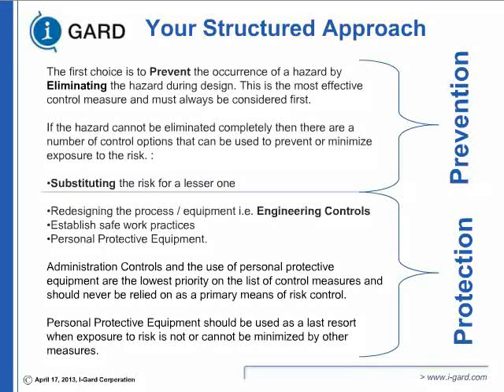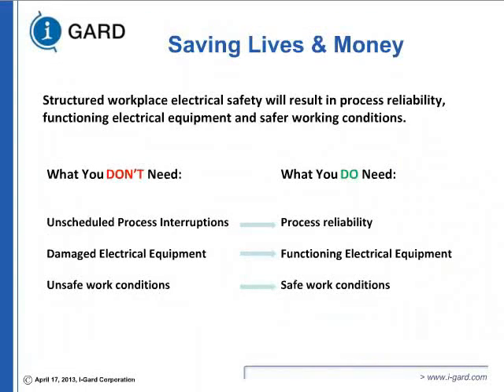Ideal is prevention, by using equipment that will prevent the fault from happening. That is the primary difference between high-resistance grounding and other protection like zone-selective interlocking or PPE. They only act after the fault happens. High-resistance grounding with second fault protection will probably minimize the risk of a fault happening. And you will all agree with me that prevention is always better than protection, even though protection is sometimes needed. So this is what you started with, what you don't need and what you do need. You don't need unscheduled process interruptions. You want to shut down when you need it. You want process reliability. Okay? You don't want to damage electrical equipment that cannot be repaired.